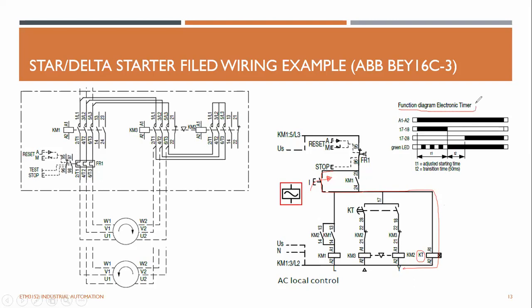You can see this is the timing diagram. A1, A2 is this coil, right? So once someone presses this one, A1, A2 energize, and at the same time the pins 17 and 18 of this timer will close. This is 17 and this is 18, and this contact will get closed. You can see now this 17 and 18 has to be operated along with A1 and A2 up to this point. So 17 and 18 close, the current will flow here, and the KM2 will be energized. The KM2 is this one.